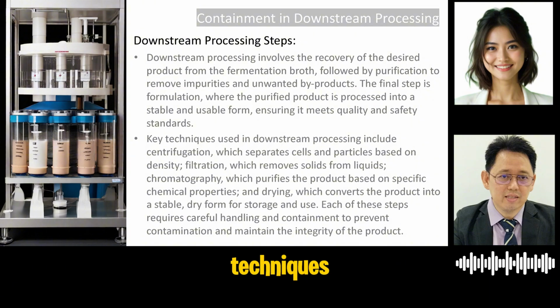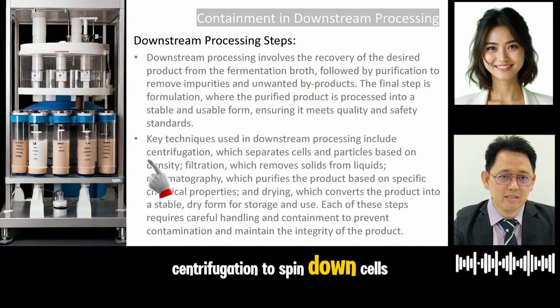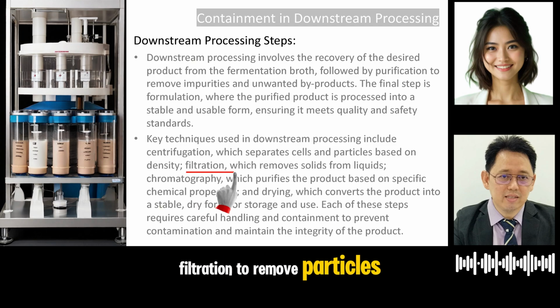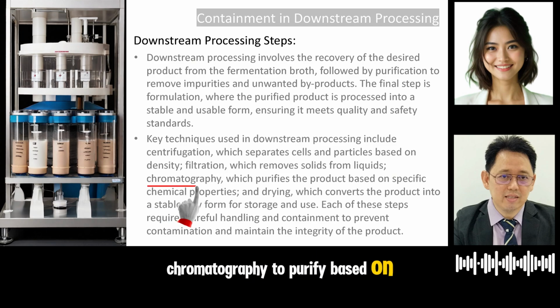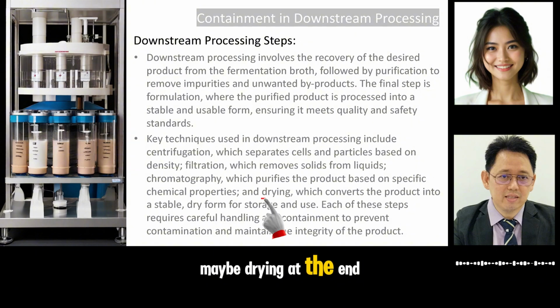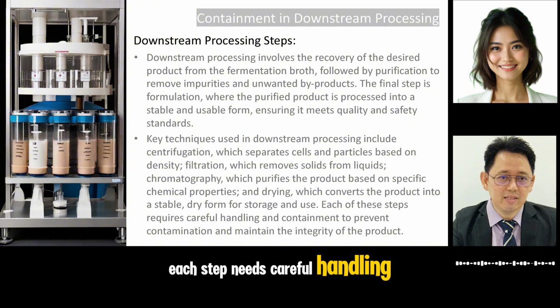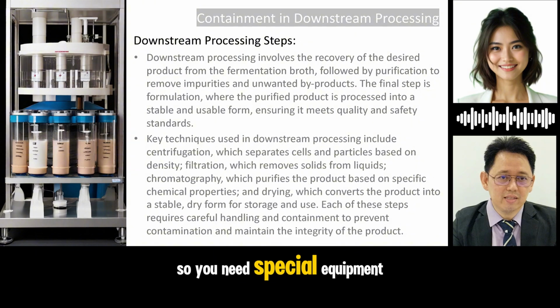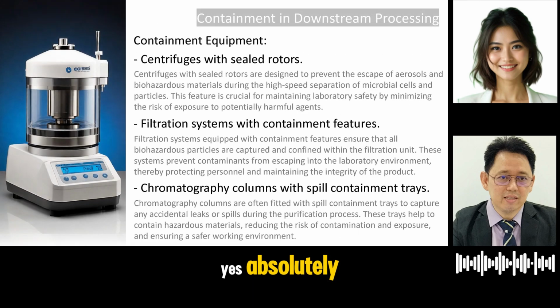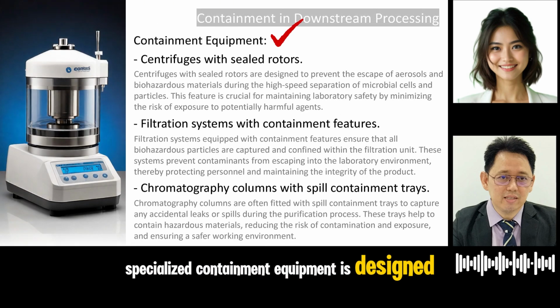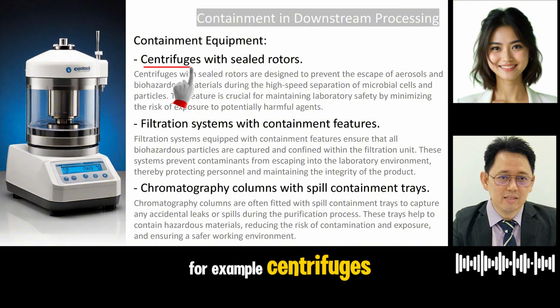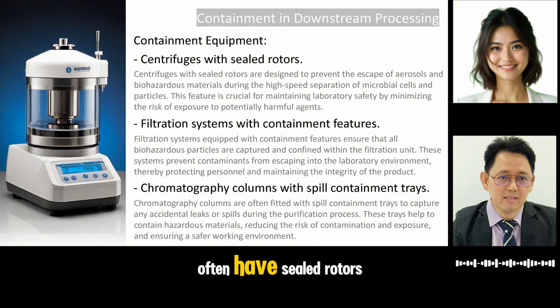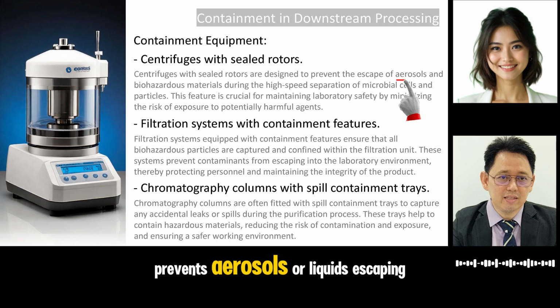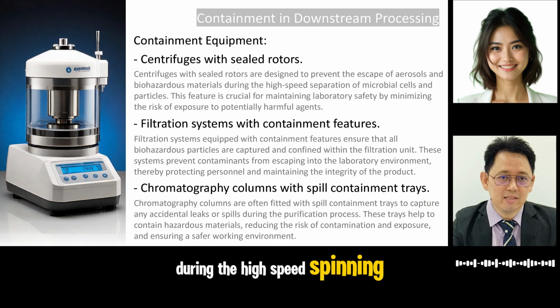Exactly. And you use various techniques: centrifugation to spin down cells, filtration to remove particles, chromatography to purify based on specific properties, maybe drying at the end. Each step needs careful handling and containment. So you need special equipment for that too. Yes, absolutely. Specialized containment equipment is designed for these stages. For example, centrifuges, especially for biohazards, often have sealed rotors. Prevents aerosols or liquids escaping during the high-speed spinning.